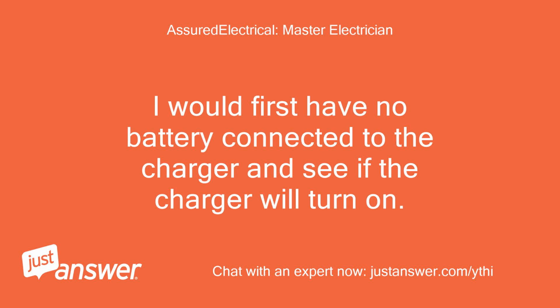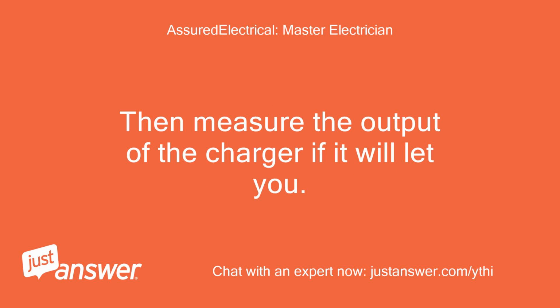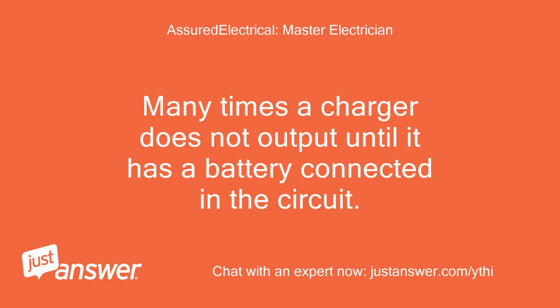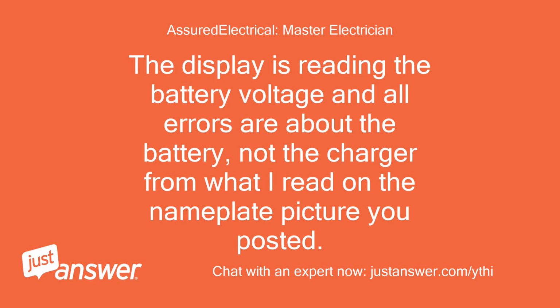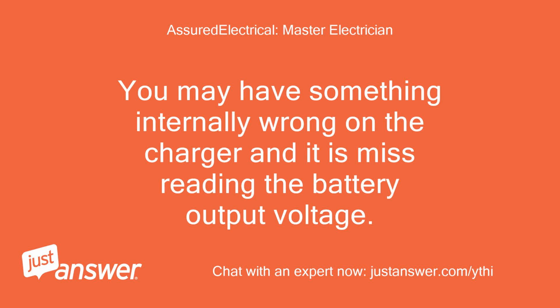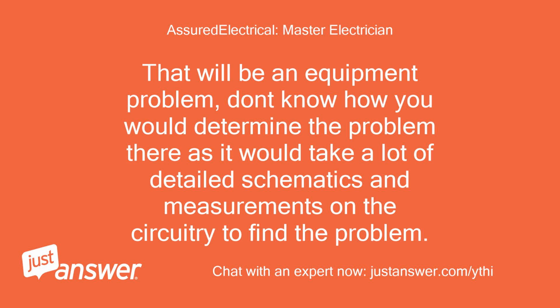I would first have no battery connected to the charger and see if the charger will turn on. Then measure the output of the charger if it will let you. Many times a charger does not output until it has a battery connected in the circuit. The display is reading the battery voltage and all errors are about the battery, not the charger, from what I read on the nameplate picture you posted. You may have something internally wrong on the charger and it is misreading the battery output voltage. That will be an equipment problem. Don't know how you would determine the problem there, as it would take a lot of detailed schematics and measurements on the circuitry to find the problem.